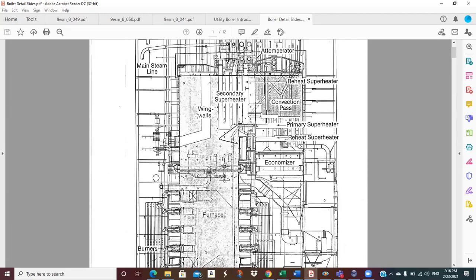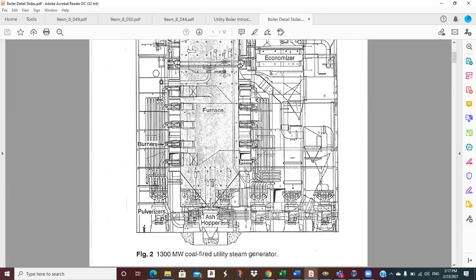And then the hot gases, so your hottest gases are flowing up through the furnace. And then this is called the convection pass. After you leave the furnace, we've got the convection pass. It comes over and down. And then at the exit, there's your economizer. And then there's an air heater, it's hard to see. There's a rotary air heater in here, and then the gases go on out. I'm not even sure, that may be the duct right there. It's a little hard to tell.